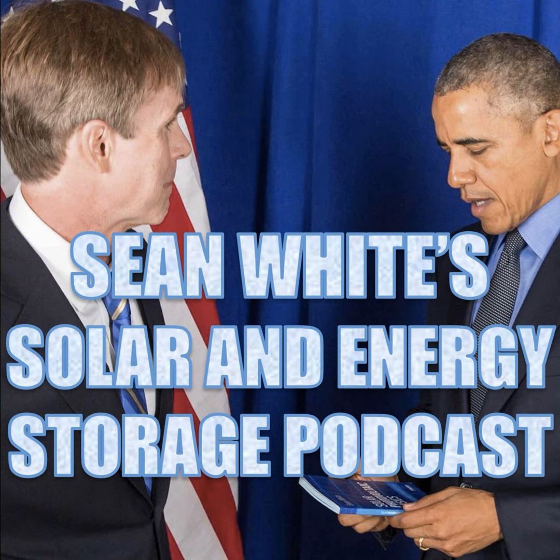And talking about the loss of the primary power source, if the grid goes down, you cannot feed the grid. Just know that. You cannot feed a grid when the grid goes down because you might hurt an electrical worker up there that's trying to fix things, and you're never going to have enough power to feed the whole grid anyway coming from your building. So you need to go into island mode. Island mode means that you disconnect from the grid. You can still work off grid, but you have to be in island mode. You can't be feeding the grid when the grid is down.